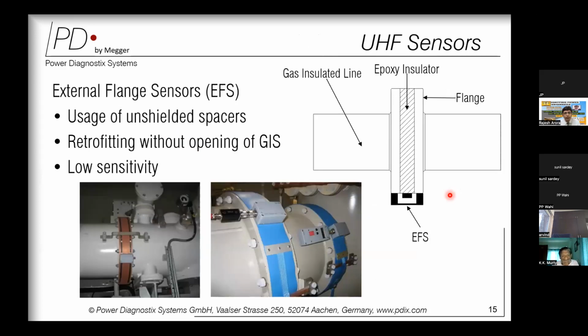When we want to do this measurement, there are various types of UHF sensors available in the market, which can be used depending upon the type of GIS we are using. Starting with an ancient or vintage GIS, which is already there in the field but did not have an inbuilt UHF sensor, if you want to do PD measurement in this kind of GIS, then we have something called an external flange sensor. These external flange sensors are retrofitted without opening the GIS, on unshielded spacers.